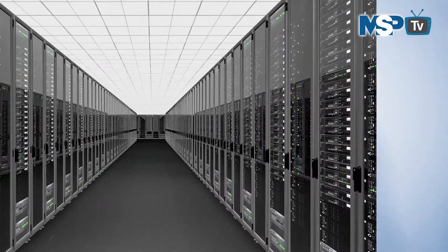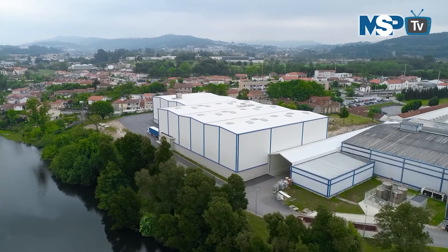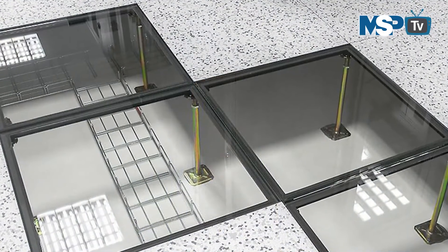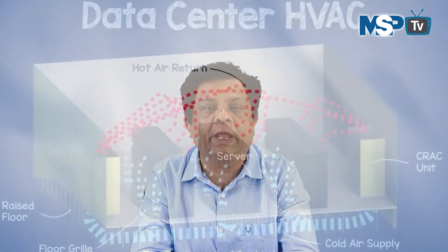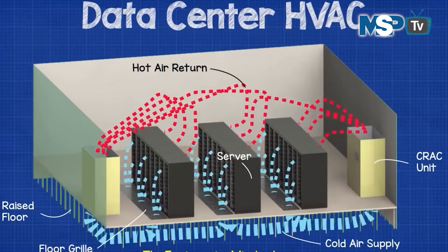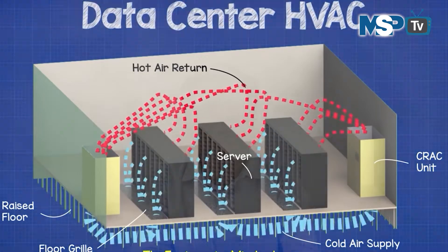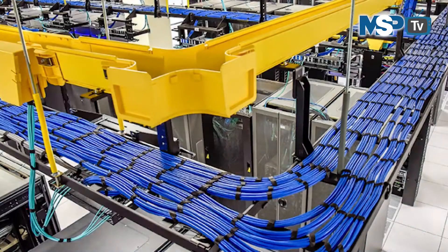Before that, let us know the importance of raised flooring in data center design. Data centers are usually built in warehouses with raised floors, but the actual floors they are built on can vary depending on the needs of its users. The data center access floor system is an important element for downward air supply — the refrigeration equipment sends cold air into the raised floor, which can evenly distribute cold air in the racks of the data center. In addition, data cables and power cables can be arranged in the space of the raised floor system.